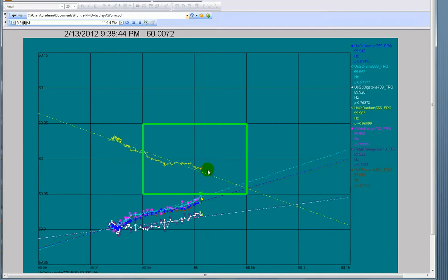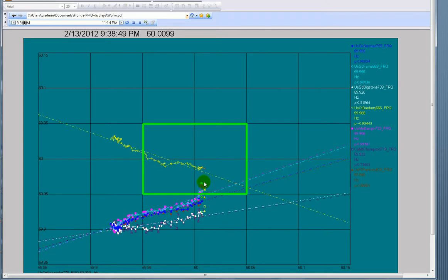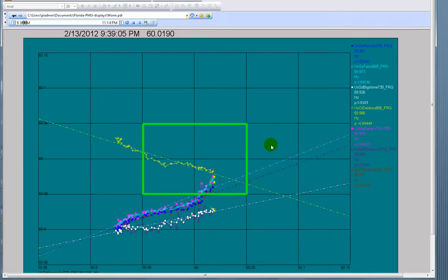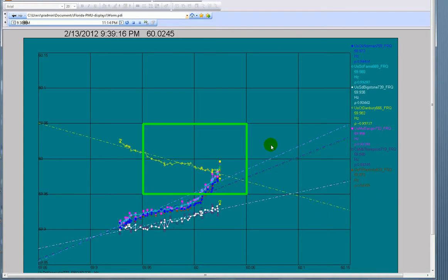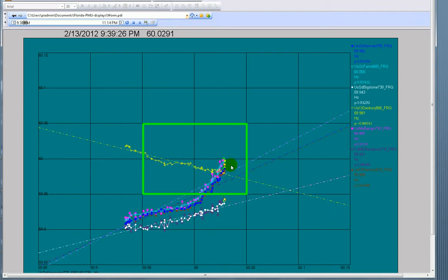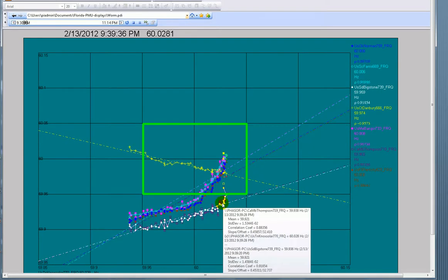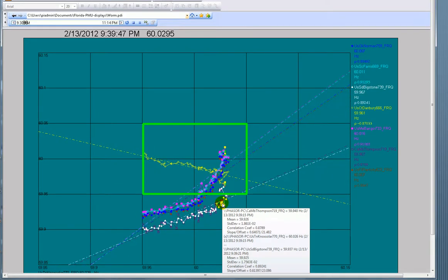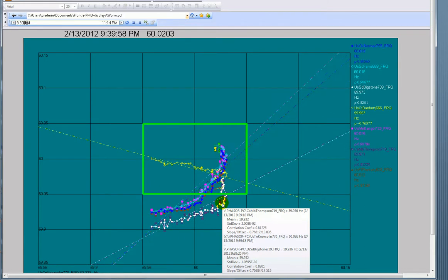You can see Danbury is operating within the standard, and now a few of the stations are getting close to operating within the NERC standards. We still have a reasonable amount of clustering. Now we have these stations that are all operating very close to synchronously. However, we have these stations which are not operating synchronously. This is in Canada and South Dakota. So Canada and South Dakota are lagging behind the rest of the Eastern Interconnection, but they're trying to catch up.